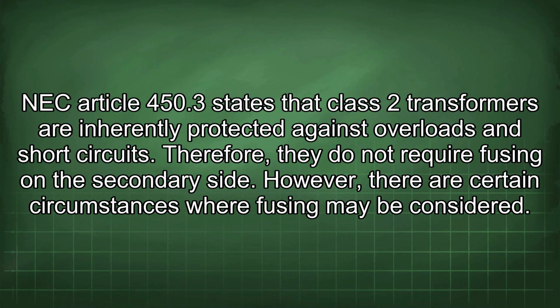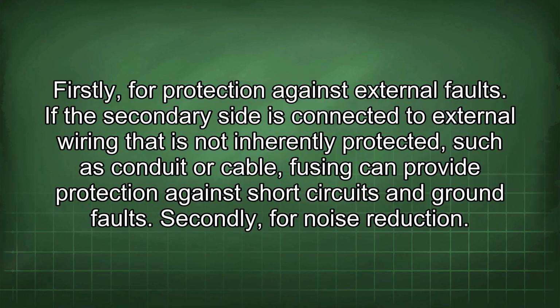NEC Article 450.3 states that Class 2 transformers are inherently protected against overloads and short circuits. Therefore, they do not require fusing on the secondary side. However, there are certain circumstances where fusing may be considered. Firstly, for protection against external faults.